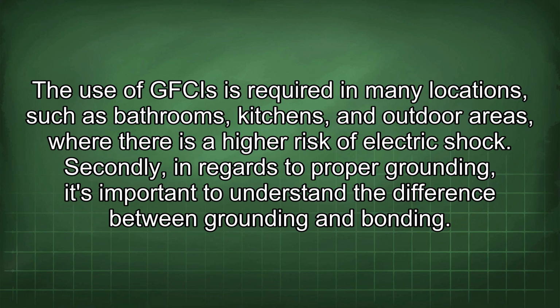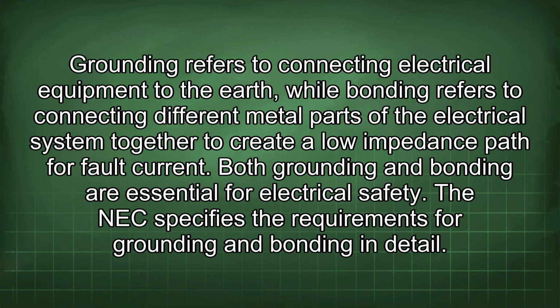Secondly, in regards to proper grounding, it's important to understand the difference between grounding and bonding. Grounding refers to connecting electrical equipment to the earth, while bonding refers to connecting different metal parts of the electrical system together to create a low impedance path for fault current. Both grounding and bonding are essential for electrical safety. The NEC specifies the requirements for grounding and bonding in detail.